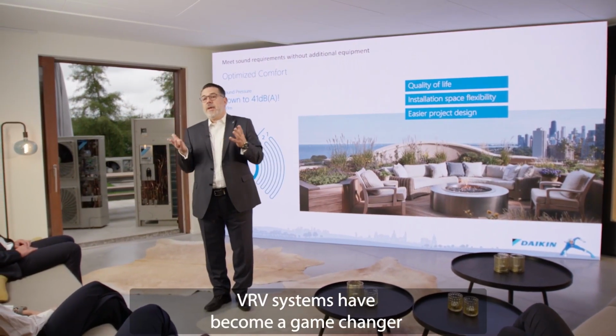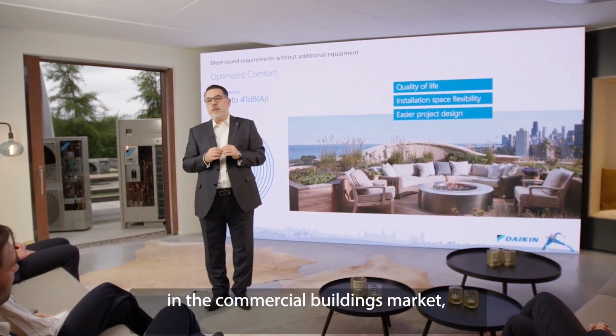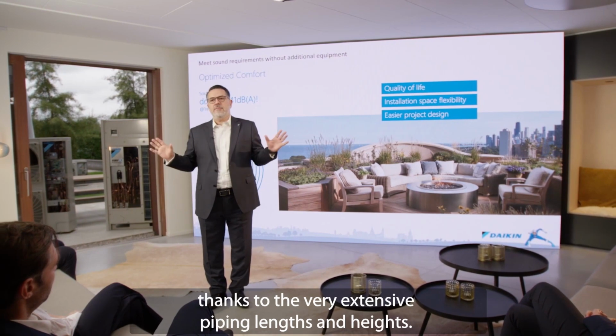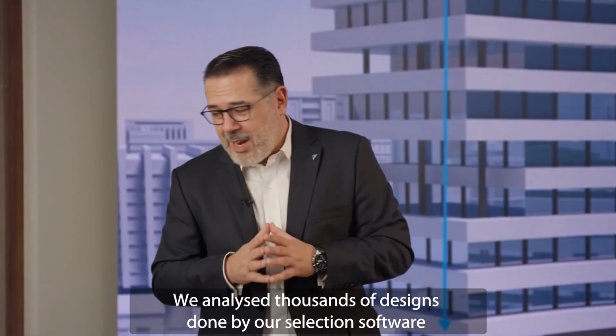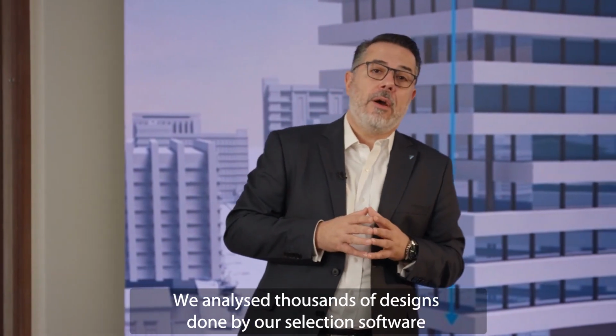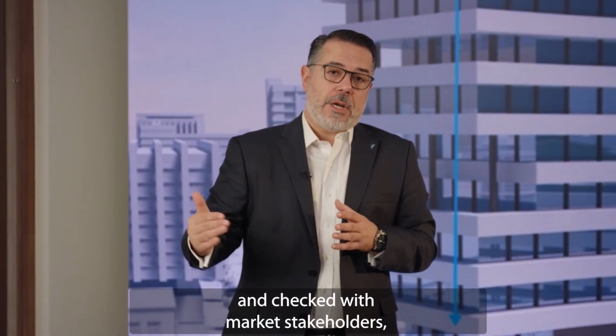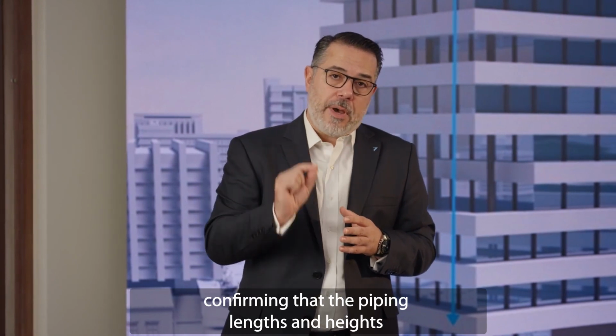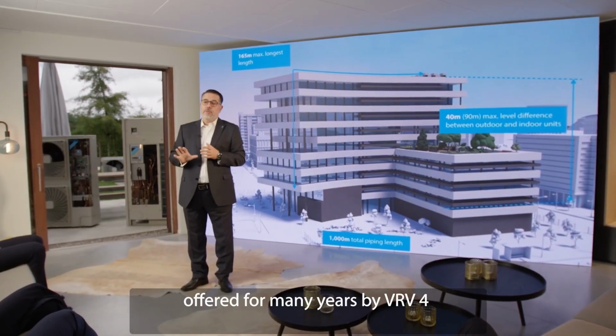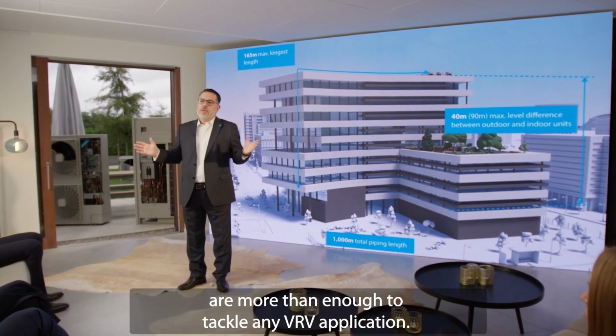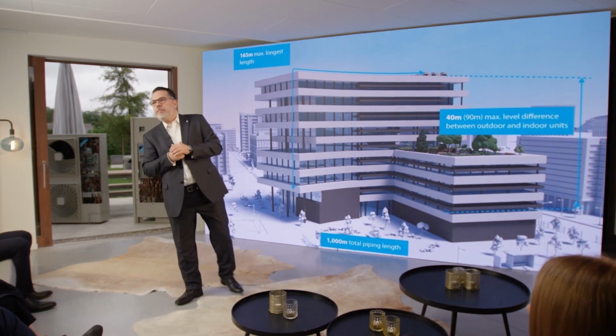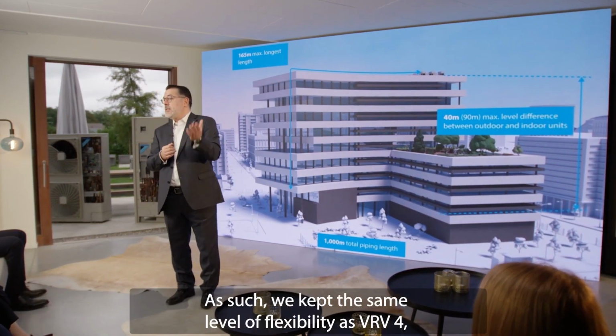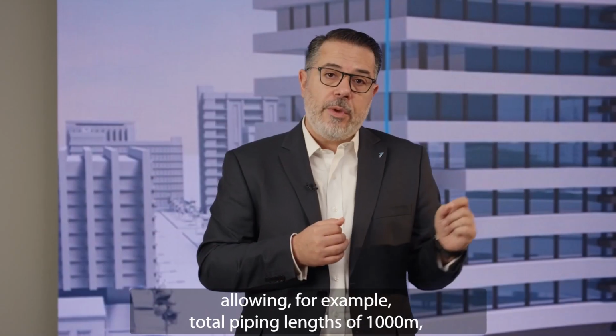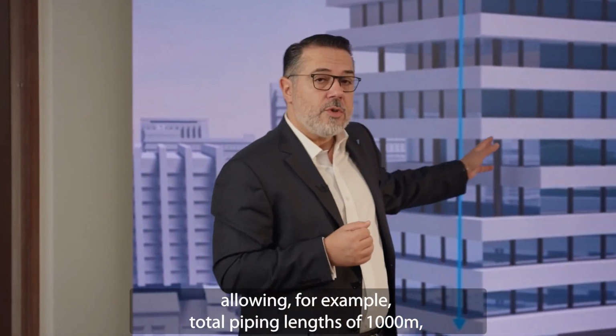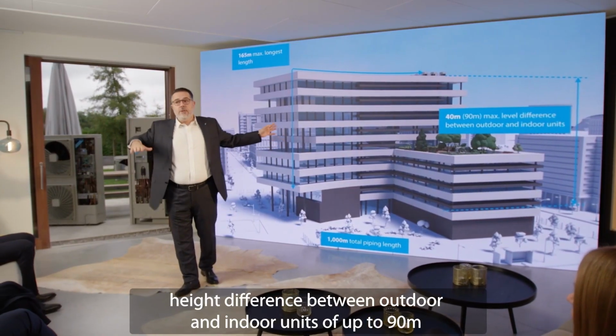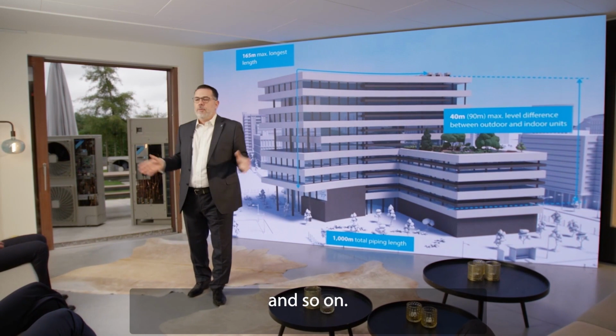VRV systems have become a game changer in the commercial buildings market, also thanks to the very extensive piping lengths and heights. We analyzed thousands of designs done by our selection software and checked with market stakeholders, confirming that the piping lengths and heights offered already for many years by VRV4 are more than enough to tackle any VRV application. As such, we kept the same level of flexibility as for VRV4, allowing, for example, total piping lengths of 1,000 meters, height difference between outdoor and indoor units up to 90 meters, and so on.